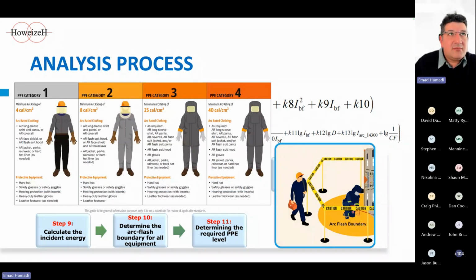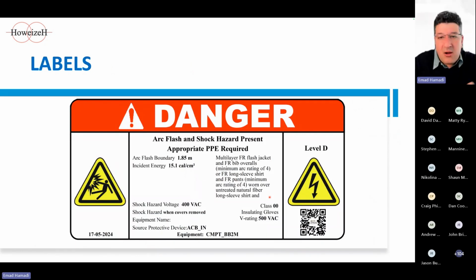And the final step is selecting the right PPE, as I mentioned earlier on, with these critical measures like category 1, 2, 3, 4 based on the guidance of the NFPA. But eventually, the type of PPE needs to be decided by the duty holder or HSE department of the company, and these are used as a guide, basically. In short, all the outcomes of the arc flash study can be summarized into the final arc flash label that can be affixed to the equipment and is essential for informing the staff about the potential hazard and ensuring safety compliance.